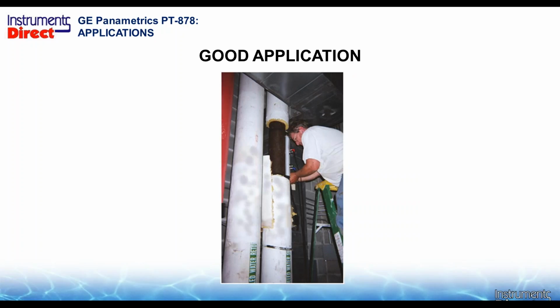A good application, even a perfect application, may require you to get some ladders or scaffolding to get to the metering point, and then you may have to actually remove insulation to get to the pipe itself. So even a perfect application may require a little work there. You may spend more time on a flow survey prepping the application than you actually spend taking the flow survey. So if you've got a job where you have to test an entire building, you may have someone go through and remove insulation and get everything set up before you even come with the flow meter.